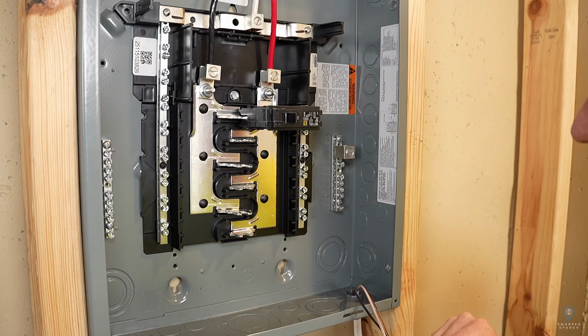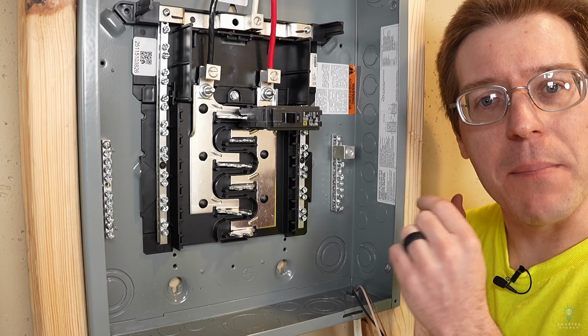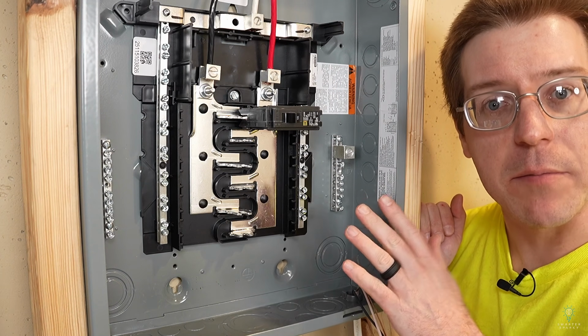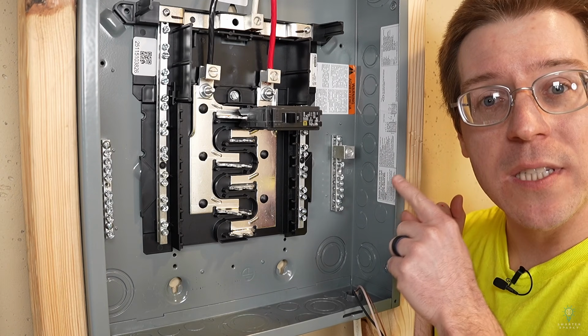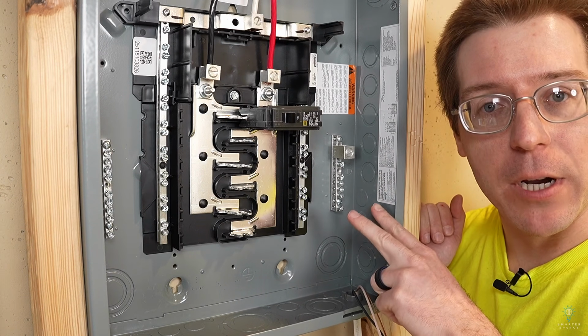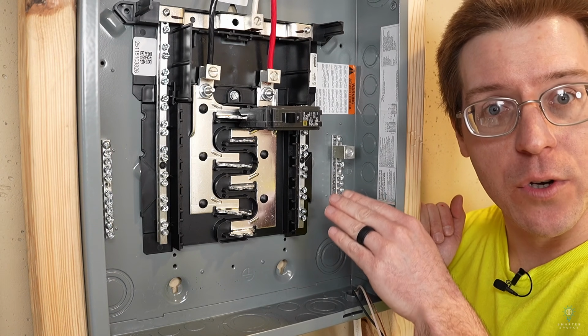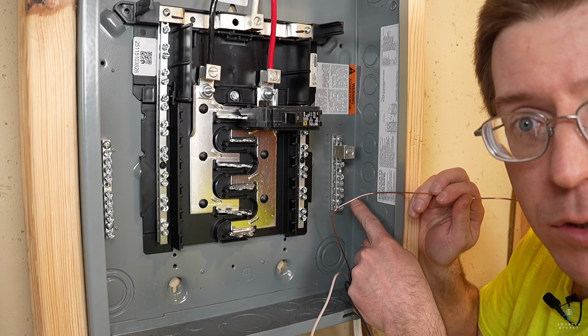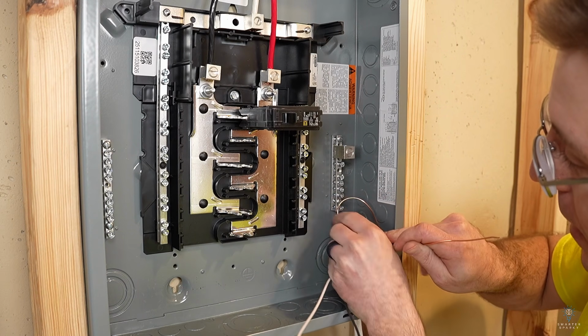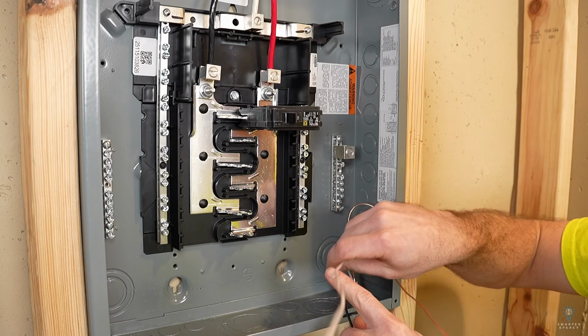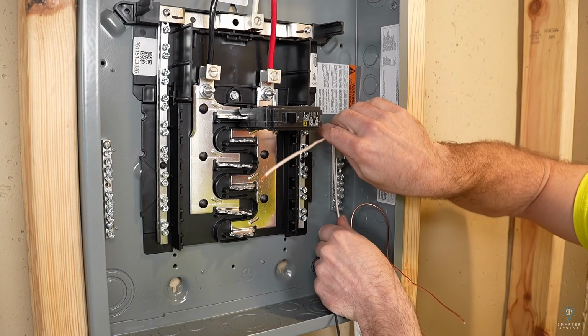It just snaps in like so. Now here's where things get a little different than the main panel. I know I've said this a few times, but it is really important. The grounds and the neutrals have to remain separate in the sub panel. They cannot share the neutral bar, okay? So our ground going to the receptacle is going to come up and land on the ground bar. Our neutral is going to come up and land on the neutral bar.